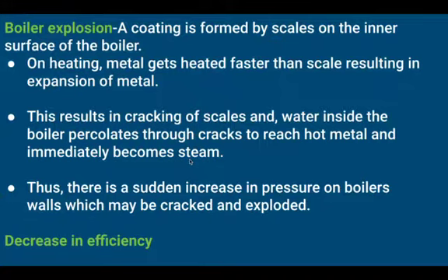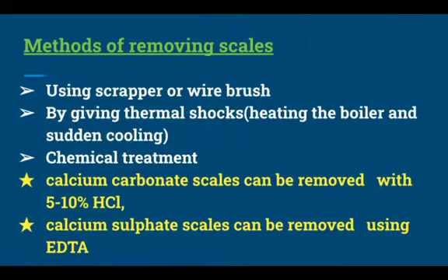So when the boiler is heated, the metal of which the boiler is made expands slightly on heating, whereas the scales present inside will not expand. As a result, cracks will be formed on the scales inside the boiler. So the water that is present inside the boiler will percolate or seep through the cracks and reach the hot metal, and this water immediately gets converted to steam. As a result, there will be a sudden increase in pressure on the boiler walls, and there are chances that it may be cracked or exploded.